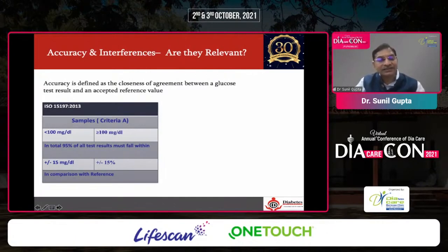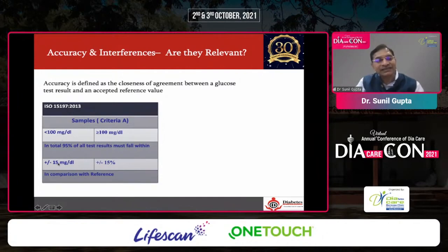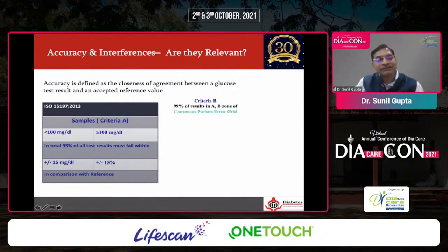These readings are then compared with a reference standard, and in total, 95% of all test results must fall within the acceptable range. If less than 95% fall within range, the glucometer is considered not accurate. When discussing the OneTouch Verio glucometer from LifeScan, 99% of results fell within the acceptable zone — more closely aligned to the comparator.